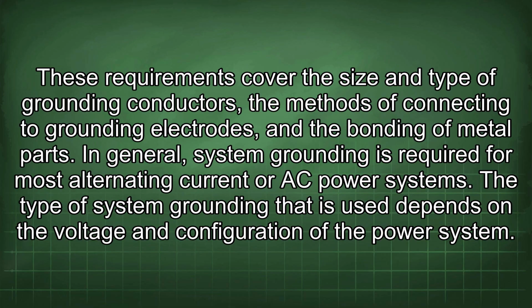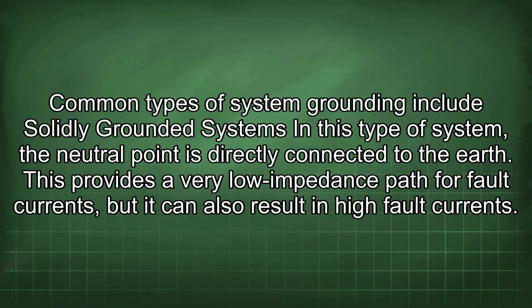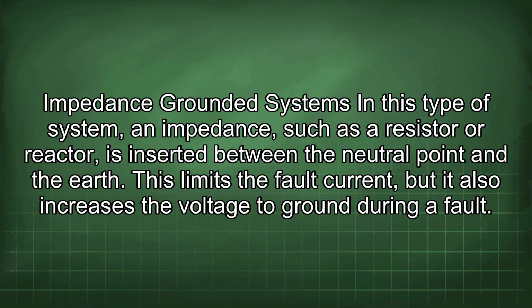The type of system grounding that is used depends on the voltage and configuration of the power system. Common types of system grounding include solidly grounded systems. In this type of system, the neutral point is directly connected to the earth. This provides a very low impedance path for fault currents, but it can also result in high fault currents. Impedance grounded systems: in this type of system, an impedance, such as a resistor or reactor, is inserted between the neutral point and the earth. This limits the fault current, but it also increases the voltage to ground during a fault.